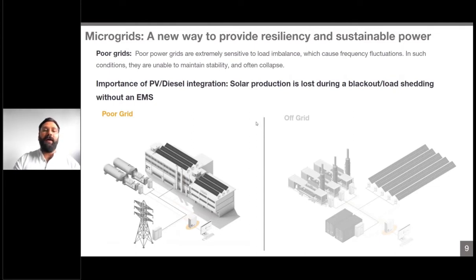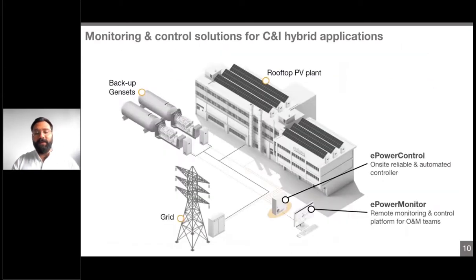So without a controller, the EPC or the client will be losing the PV production. So it is needed to have an EMS in order to integrate the PV with the gensets, and by that increase the solar penetration and reduce the fuel consumption. This is the standard configuration where we have a grid and the genset as a backup. Our controller will be connected directly to the different equipment: directly with the PV inverters through Modbus protocol, with genset controllers, and with the grid using some meters. I'll be discussing the features in the next slide, but I want to focus here on the fact that with all our controllers, we also provide a monitoring system for all the KPIs of each equipment.